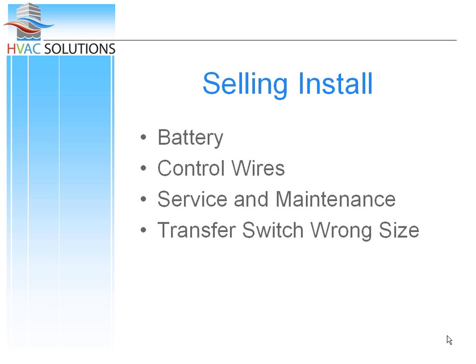One of the other issues we've seen is the transfer switch being the wrong size. It doesn't sound like a big deal, but I've had situations where a guy looks at a generator, let's say it's a 15 kW putting off around 80 amps. So the guy puts in a 100 amp transfer switch. So 15 kW, 100 amp transfer switch. Problem is, the house is 200 amps.